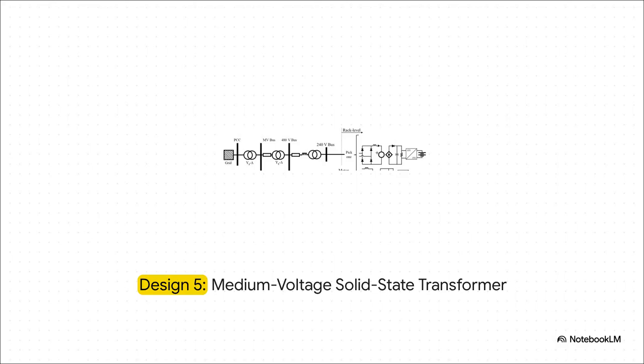And this brilliantly illustrates the near-future Design 5, the Medium Voltage Solid-State Transformer, or SST. To pack even more power into an even smaller footprint, engineers are replacing those bulky standard magnetic transformers entirely. The solid-state transformer directly steps down medium voltage power straight to DC for the racks in one highly efficient step. This is a real game changer and a major research and development focus right now.